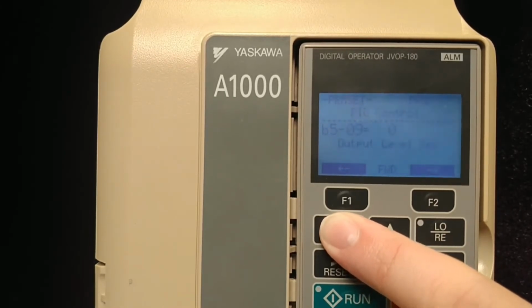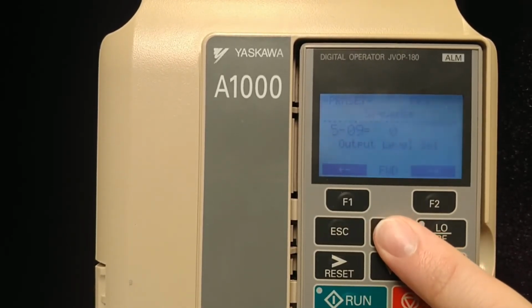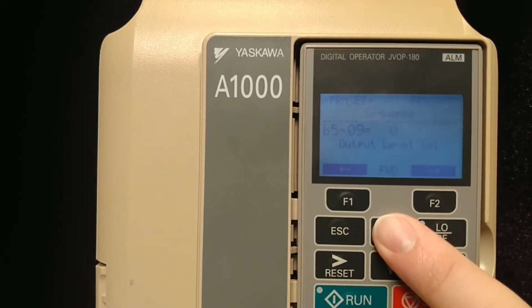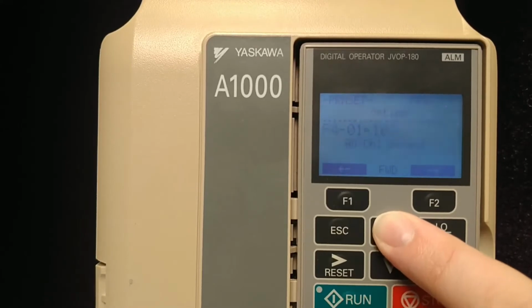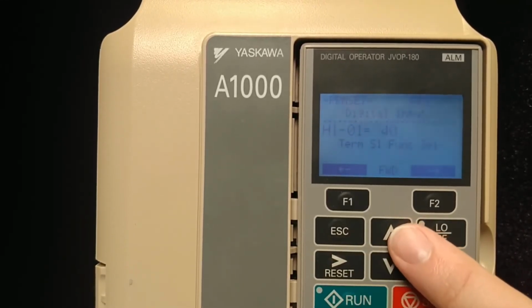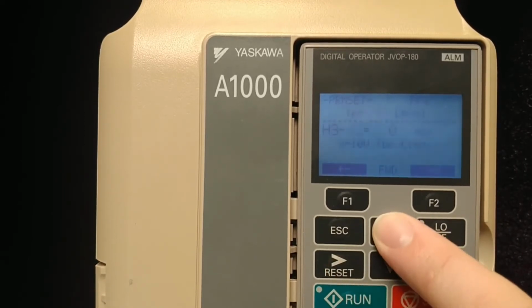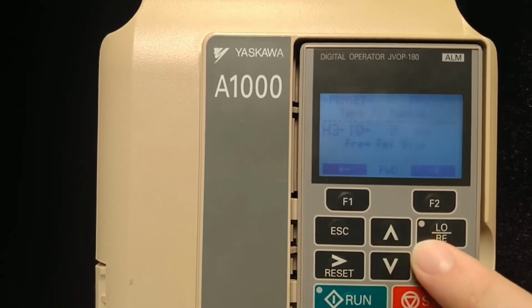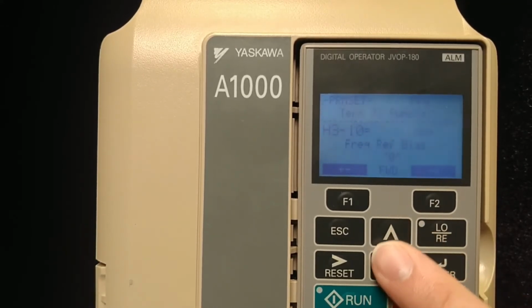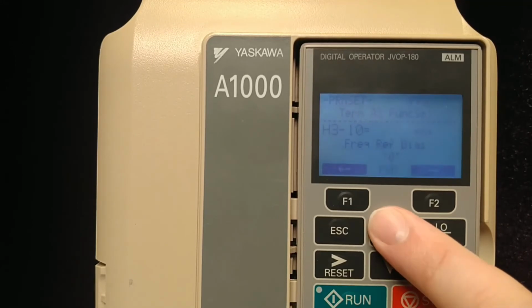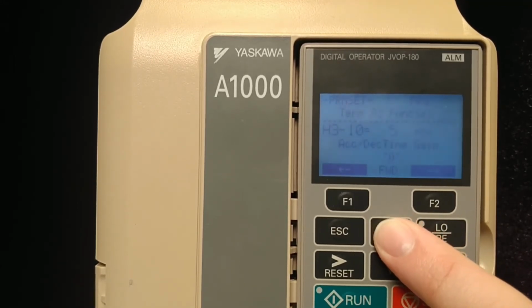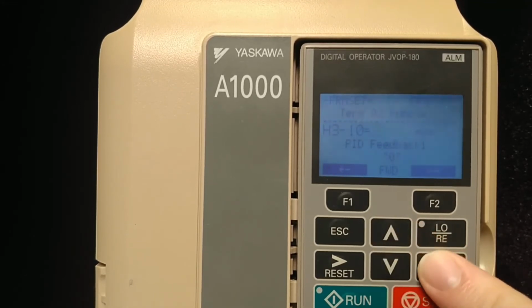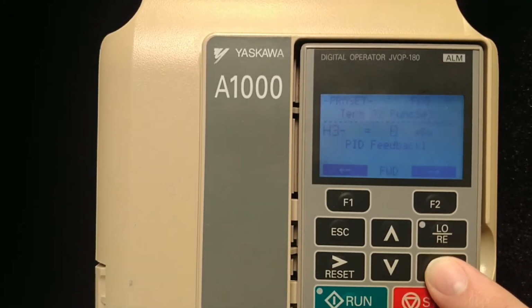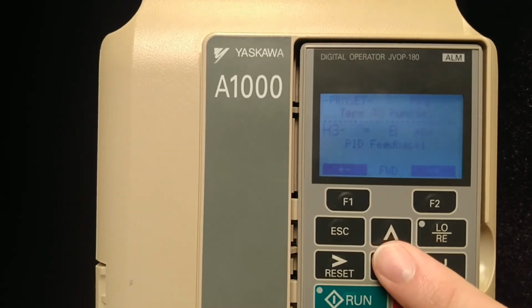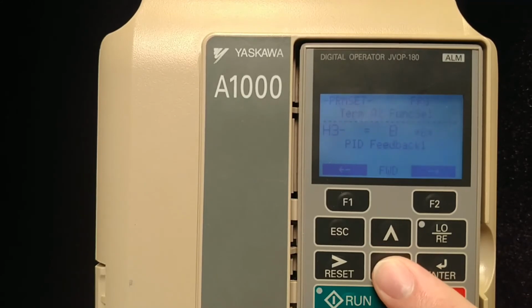The last parameter that we'll have to check will be our analog input setting. Assuming we're using analog input 2 on the drive, that parameter will be H3-10. H3-10 is the function for terminal A2. Normally it's set at frequency bias. We would change it to a B for a PID feedback input. Now our A2 input is selected as PID feedback, and by default the A2 input is set for a 4 to 20 milliamp signal.